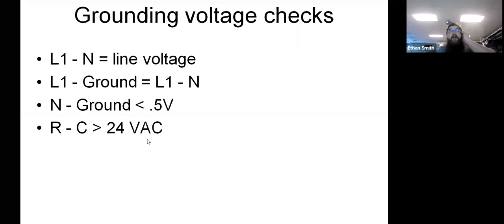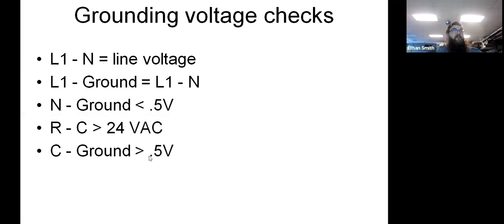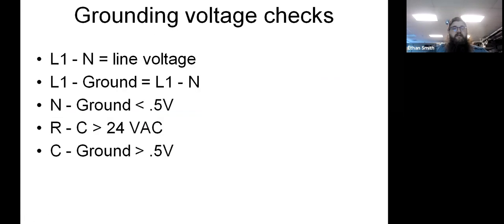So we talked about that. The old rule used to be half a volt. On your low voltage, you can go R to C, you should have 24 volts. Common to ground should again be that same as your neutral to ground. Okay, so there's your voltage checks for grounds, guys. Both your high and your low voltage system inside a furnace needs to be grounded properly. Okay. Any questions about grounds or anything like that, guys, that we've covered?